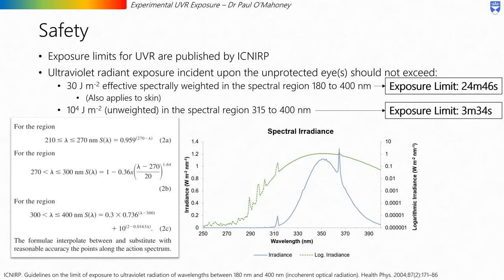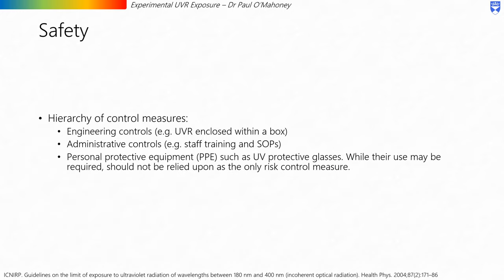The time presented here is the maximum exposure duration in an eight-hour period. This is of course a limit and all reasonable measures should be taken to reduce unnecessary UVR exposure. All UVR sources should initially be checked through non-UVR outputs and should be risk assessed accordingly. In the hierarchy of control measures, engineering controls are the preferred option and include the UVR being enclosed within a box or an interlock on the lab. Administrative controls can be put in place, including staff training and SOPs. Lastly, personal protective equipment such as UV protective glasses may be required, but should not be relied on as the only risk control measure.